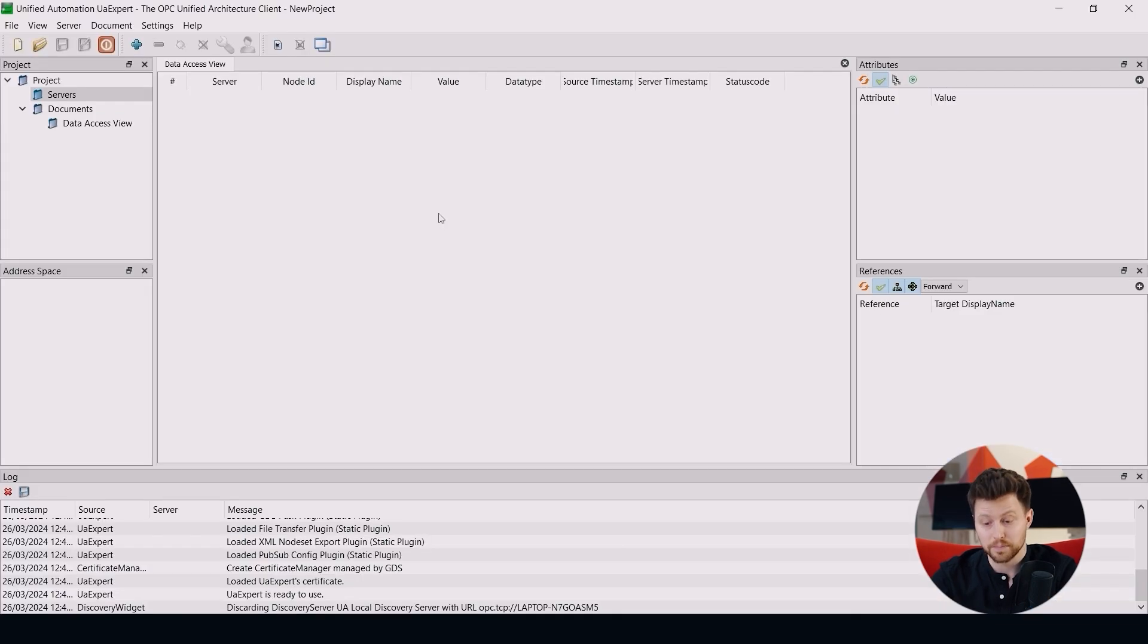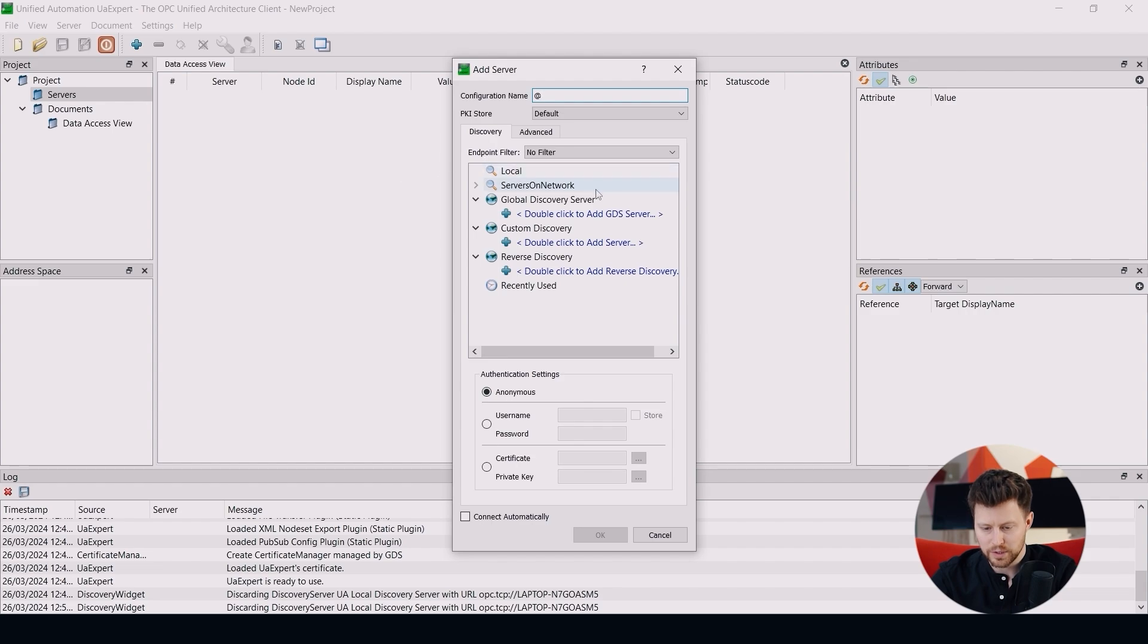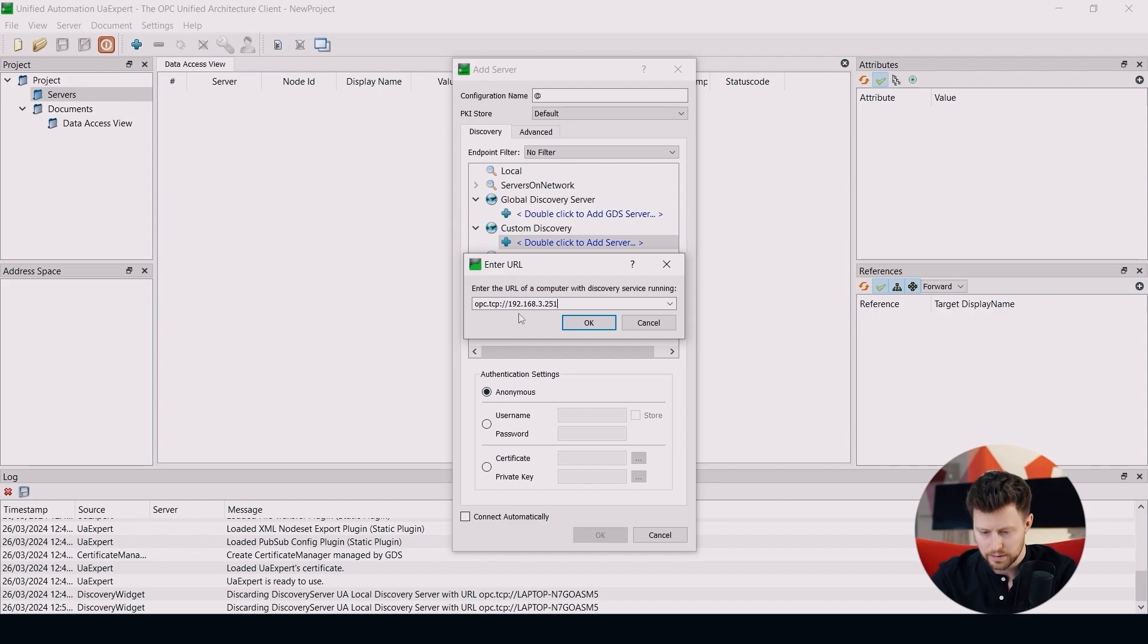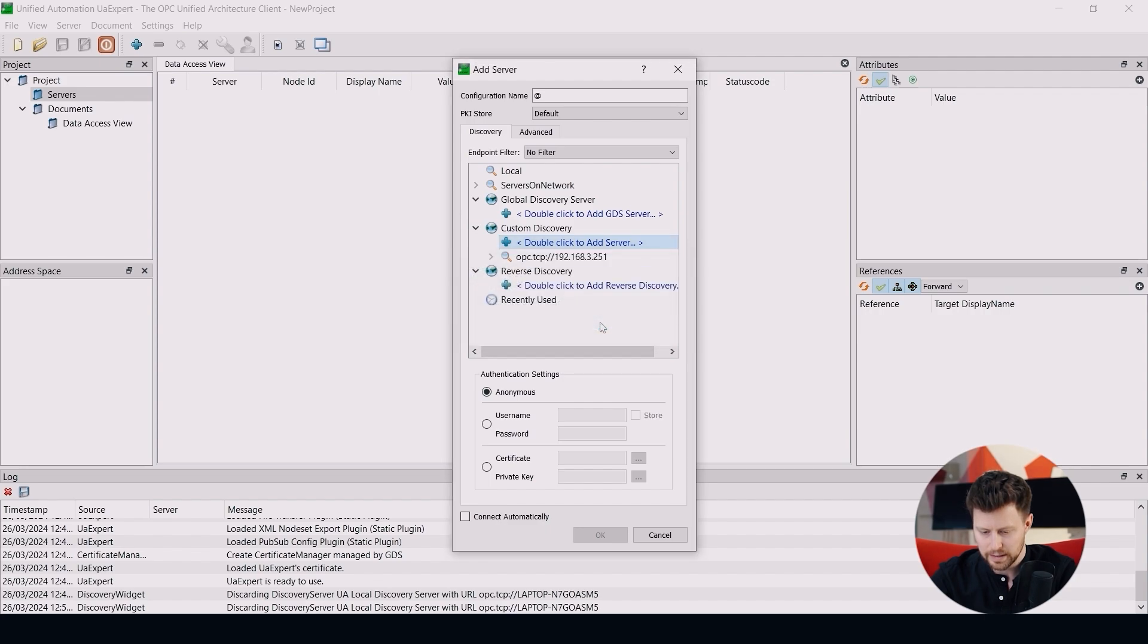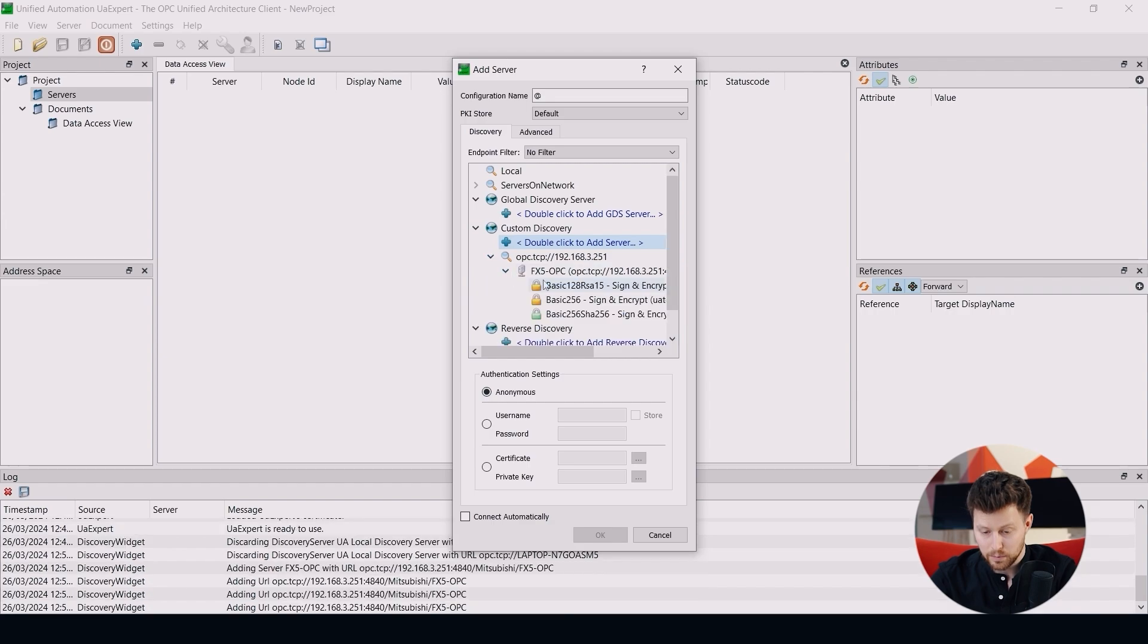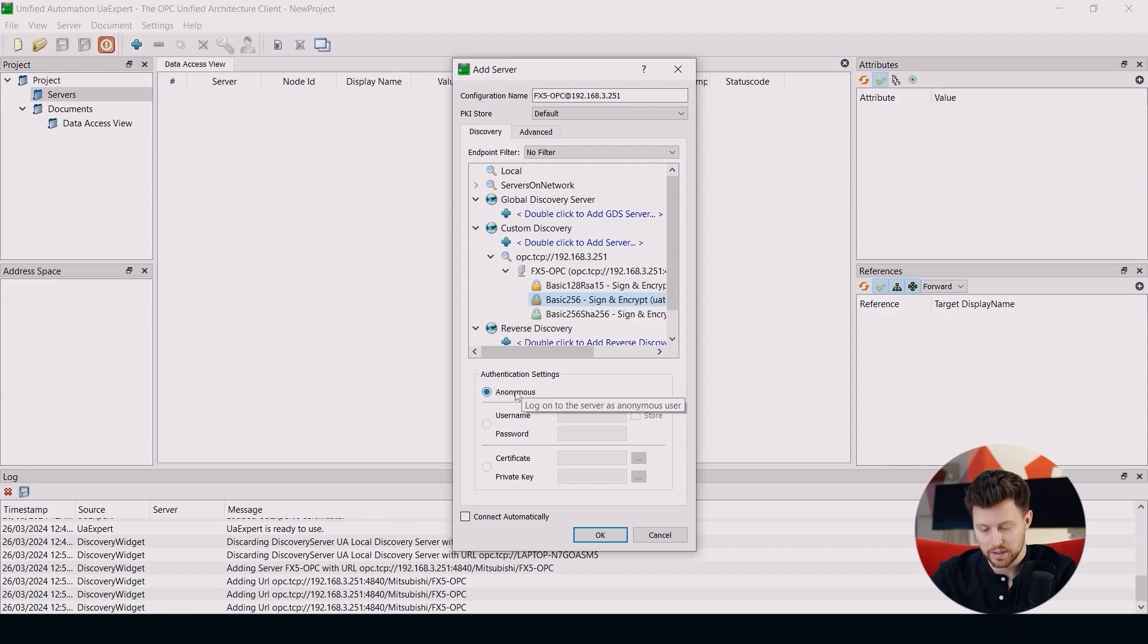So to configure OPC client, please open the UA expert again. And here we have to add our server. So right click on servers, add. And here we choose the custom discovery. Here we just put our IP address of FX5 OPC module that we configured. And click OK and OK. We can also choose the security policy. I will choose this one. And then we can also choose the authentication settings for users. I will choose the anonymous version.